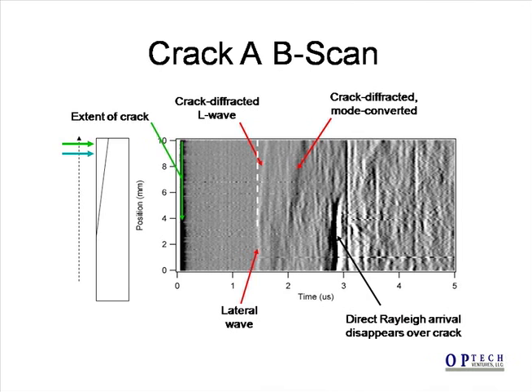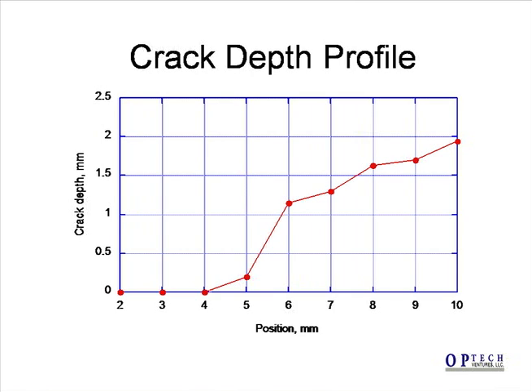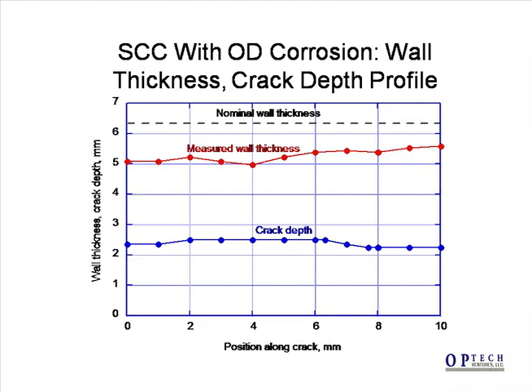We also observe a mode-converted arrival. Using the B-scan data and the measurement scheme described earlier, we have plotted the crack depth versus position. The crack deepens along the scan and reaches a depth of 2 mm at the end of the scan. We scanned another crack at a position where there was significant OD corrosion, and we were able to measure the wall thickness along with the crack depth. This enables a realistic determination of the crack depth as a fraction of the remaining wall.